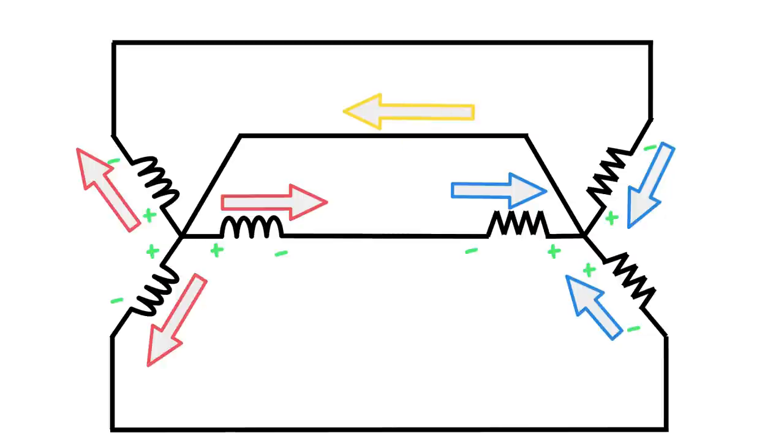Now, just to quickly talk about this neutral. What will happen is the currents will all converge at this star point, and then you will have a neutral current that comes along here. Now, not to confuse you too much, but if all these three are balanced, this neutral current here will be 0 amps. If they are unbalanced, then the neutral will carry a current, just doing what a neutral does.